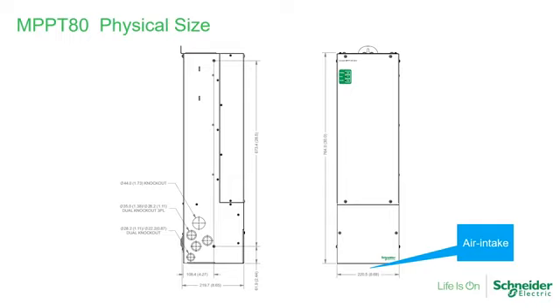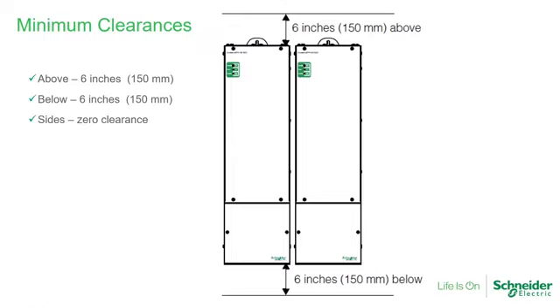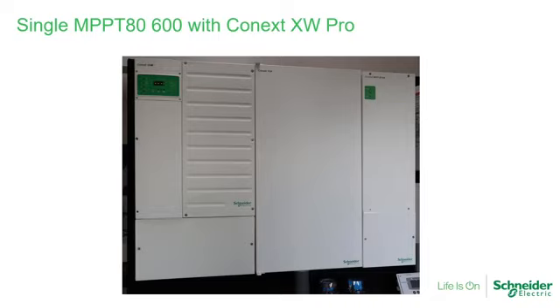And the very bottom, you will find a screen and no knockouts, because this is where the unit will actually have air intake. Don't block the bottom because that's how the unit ventilates. You'll have 2 fans on the top, and so it is extracting or pushing the air up. So for that reason, you need to give the unit a minimum clearance from the top and the bottom. And here I'm showing you a dual, and you see them side by side. That's perfectly okay, because there's no air movement on the sides. So as long as you leave enough space from the bottom and out to the top for the fans to move the air. This is what a real system looks like. It was designed as exactly the same size as the PDP, the XW Pro PDP combination.